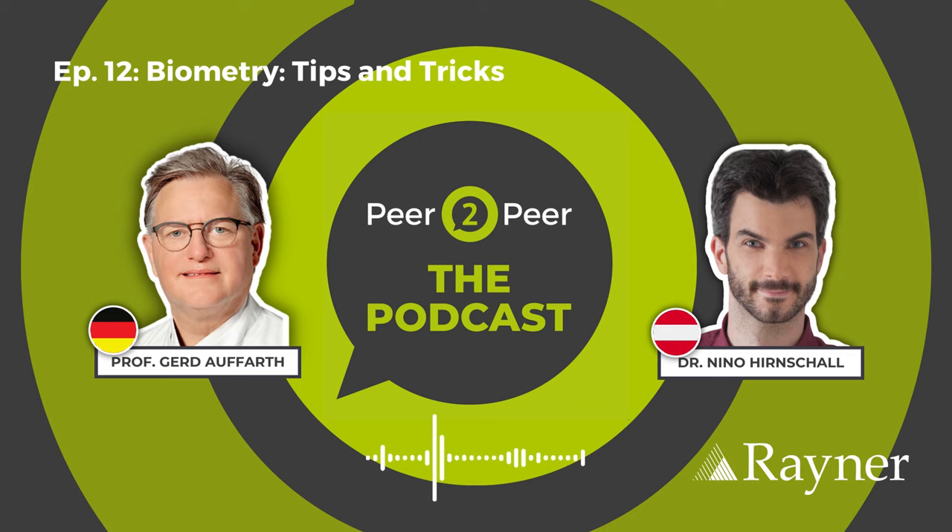Would you agree with that? Yes, I would. When we look back, we actually separated measurements in former times. We had, for example, immersion ultrasound measurement, then we used the Javal or whatever for keratometry. Then we had a machine like the IOL master that did everything. Nowadays we get more and more information. We even have OCT technology so we can look at least at the macula qualitatively. Don't you think that biometry has completely changed from just data for lens calculation to a comprehensive diagnostic system?